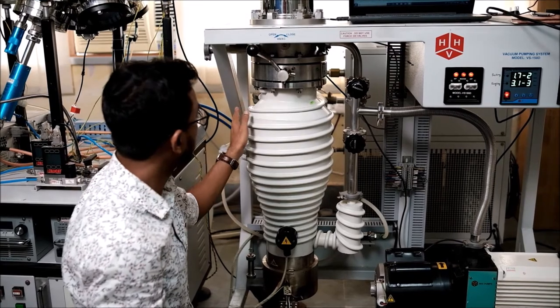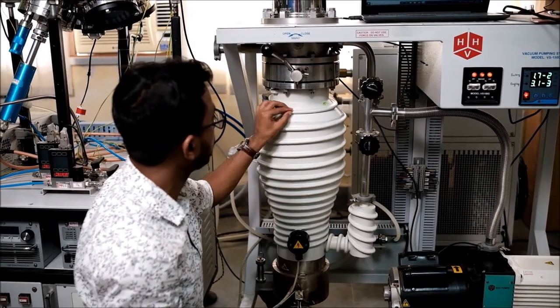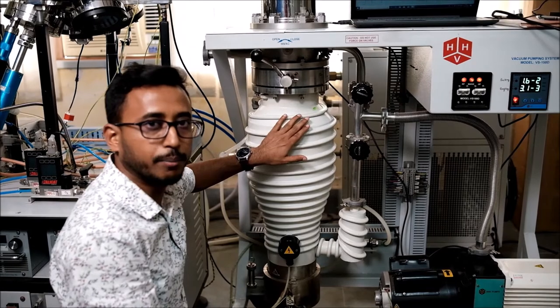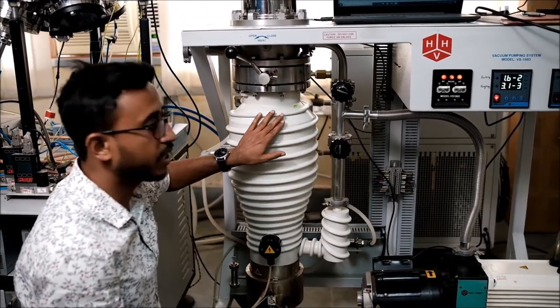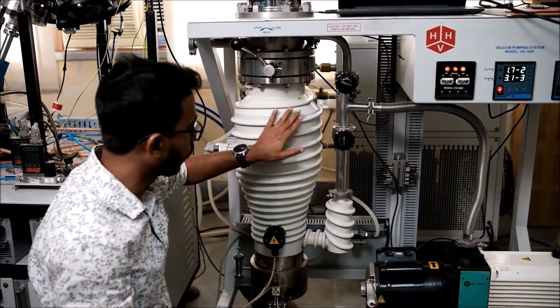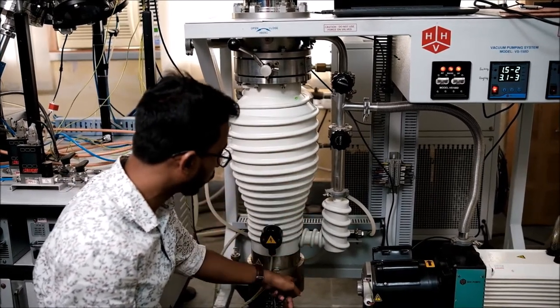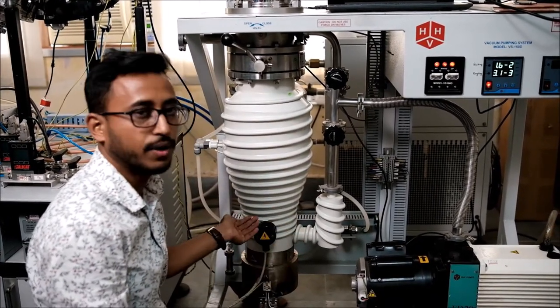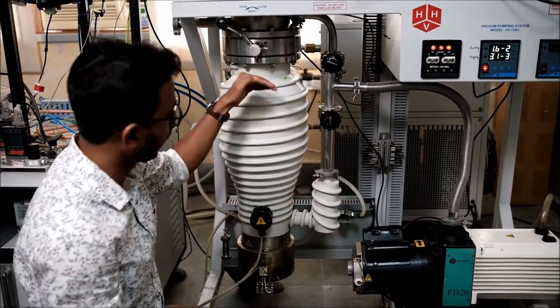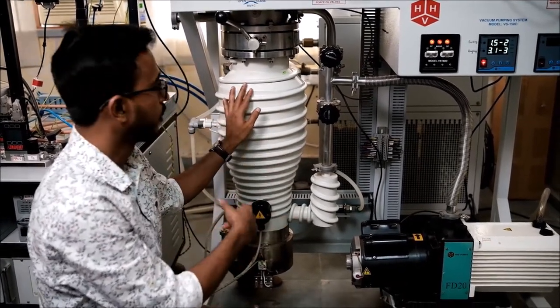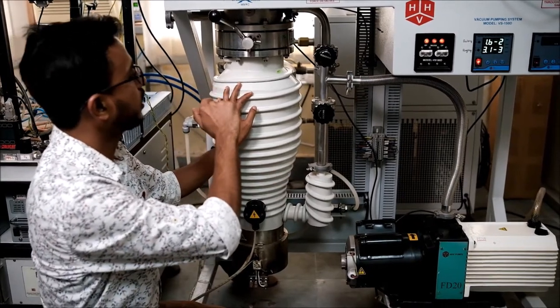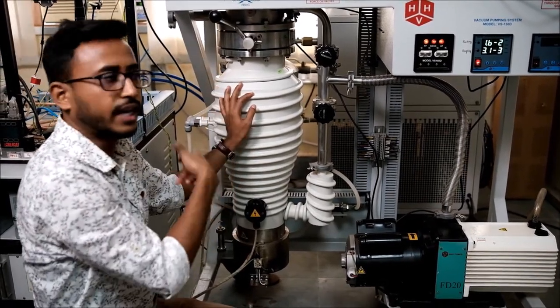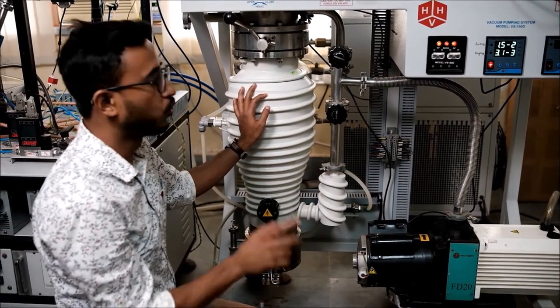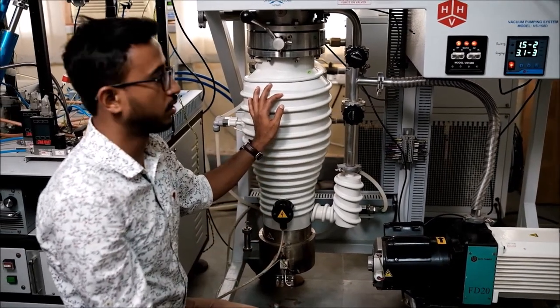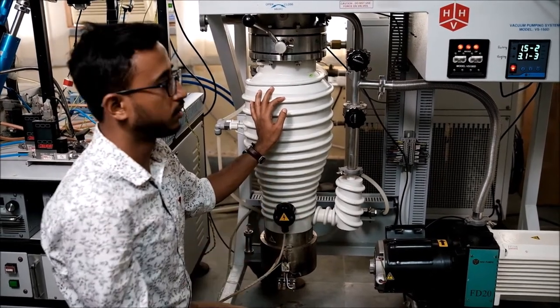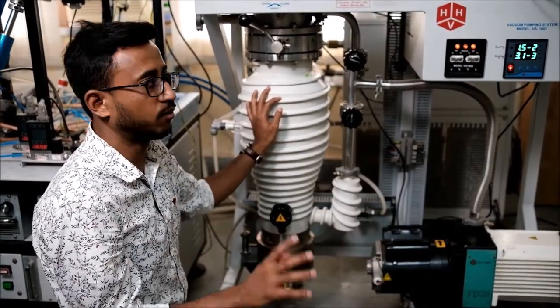And at the wall of the diffusion pump chamber, chilled water is passed through so that the wall is maintained at low temperature, so that the vaporized oil can be condensed into a liquid form and again goes back to the bottom stage. Then again it heats up and forms a vapor and then a jet, then again condenses, and this cycle goes on. This way we get a very low pressure, and for this chamber it takes more than an hour to go to 10 to the minus 6 millibar of pressure. So we will meet after some time when the pressure reaches the 10 to the minus 6 level.